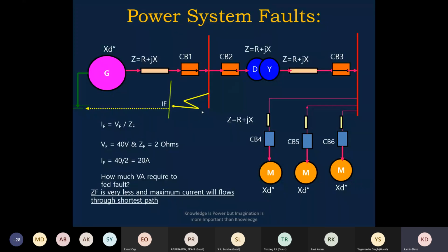800 VA is higher than the 100 VA, because source capacity is 100 VA and the required VA to feed the fault is 800 VA. That is called the fault condition, because the source does not have the capacity to feed the 800 VA continuously. The short-time rating is either for 1 second, or 1.5 seconds, or 2 seconds maximum. So that is called the abnormal condition or fault condition.